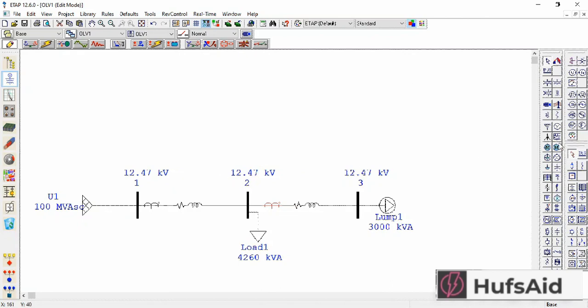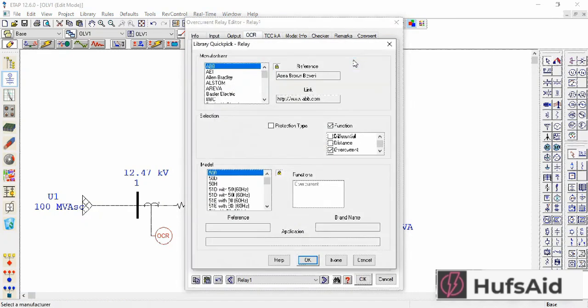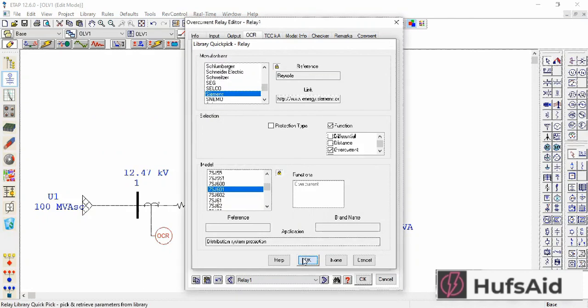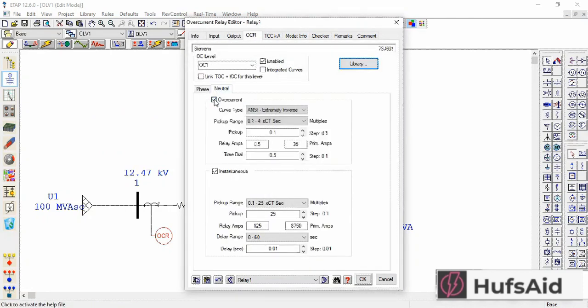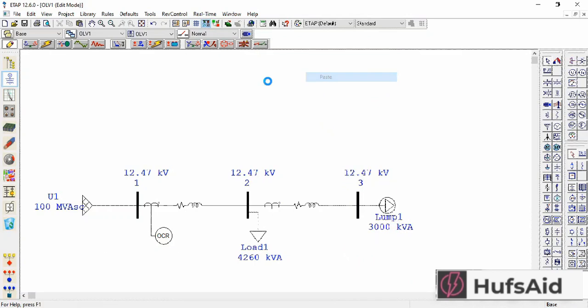Now let's connect the overcurrent relays to these CTs. I will select from the OCR library the Siemens 7SJ601. It has an overcurrent function — I am deselecting overcurrent and just leaving the instantaneous function, and I'm going to paste it to the other CT as well.